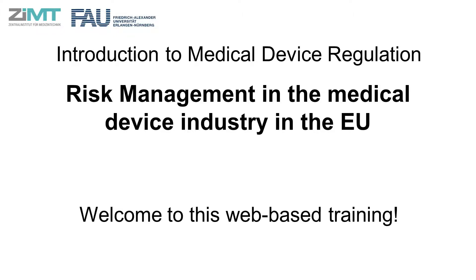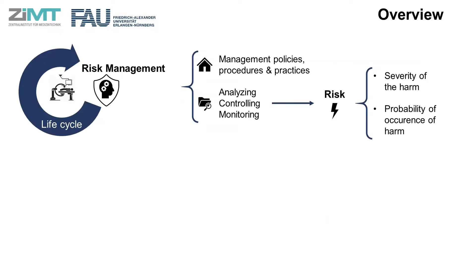Welcome to this web-based training. Risk management is defined as the systematic application of management policies, procedures, and practices to the tasks of analyzing, controlling, and monitoring risk, where risk is defined as the combination of the probability of occurrence of harm and the severity of that harm. Risk management is an essential requirement of any medical device life cycle, encompassing the initial design and development phase and all post-market activities through to decommission and disposal. It is not a static process and requires regular systemic updates.